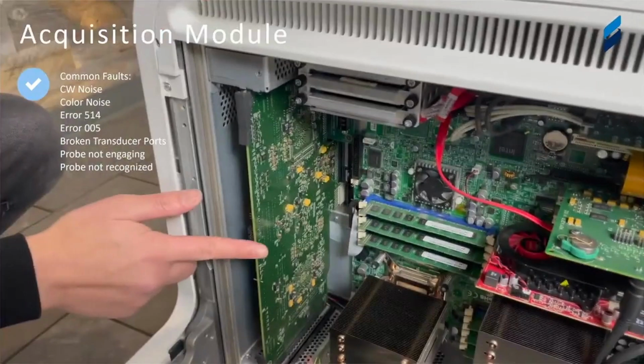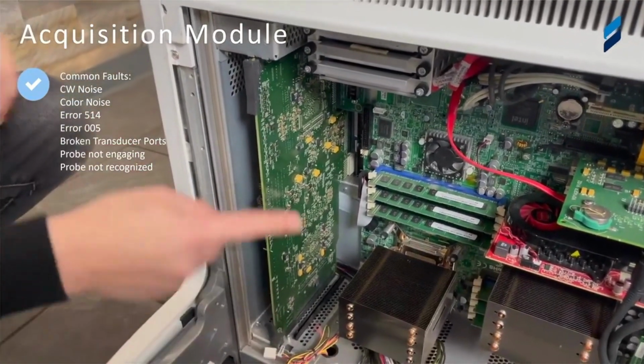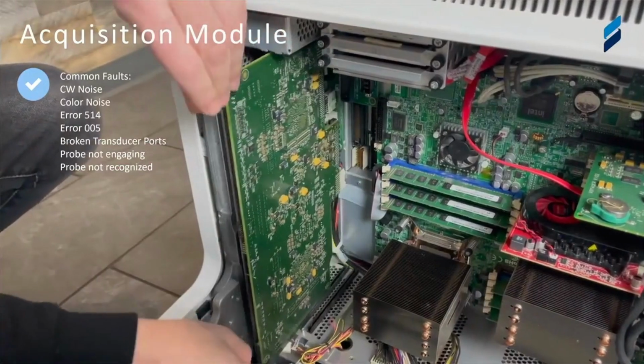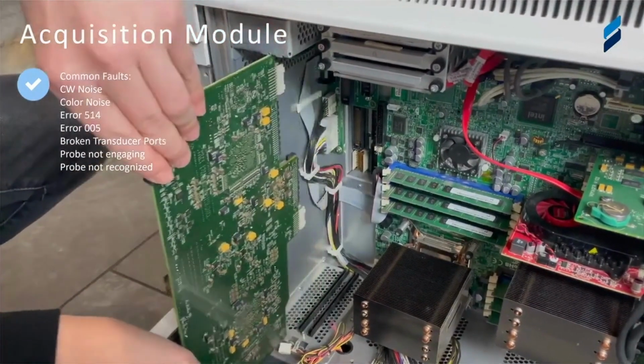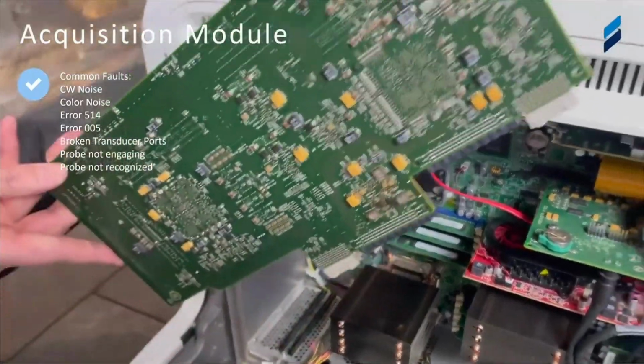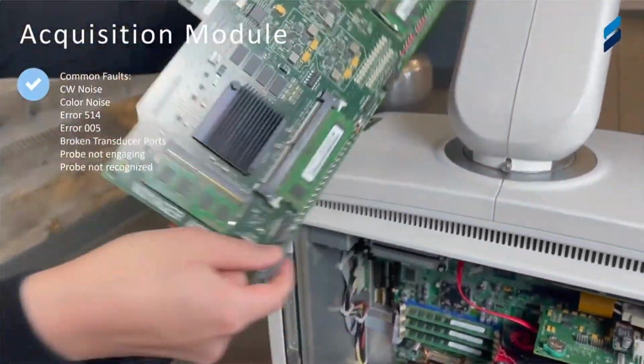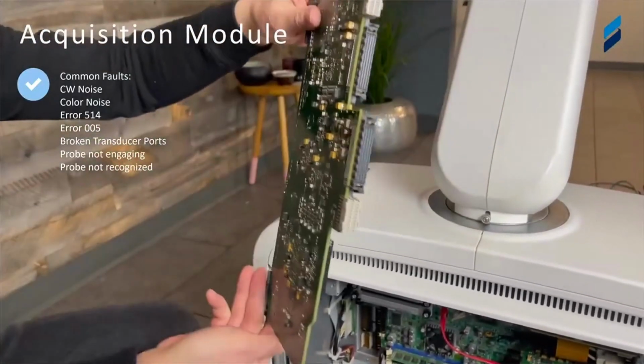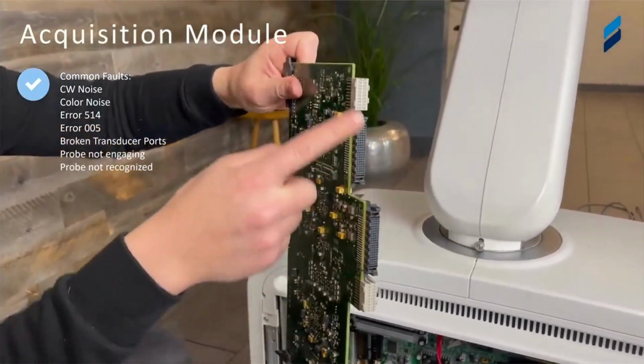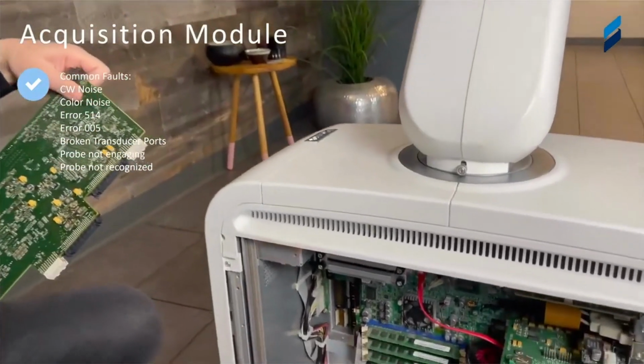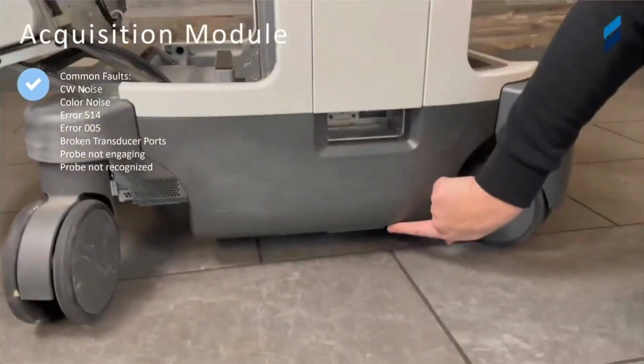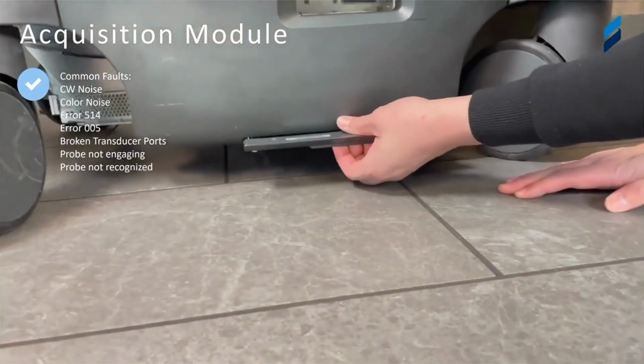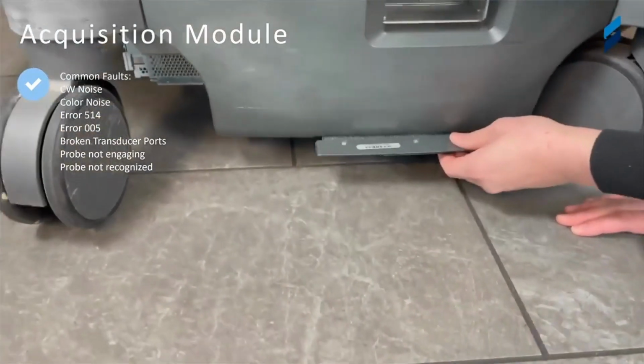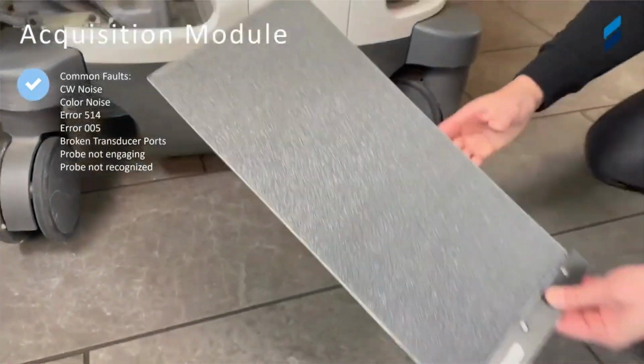Power regulator boards coming out. Those three connectors we just removed were fan speed connectors, or fan power connectors, I should say. This is the ACB, and the connectors I was just connecting to up front is the acquisition module itself. So removing these so the acquisition module can dismount from the front, otherwise it's connected to these boards.